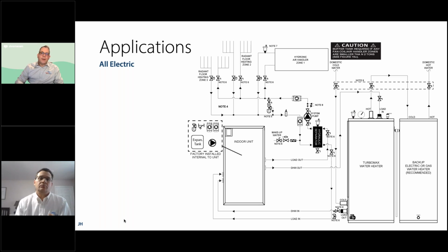So very simple piping. All of the hydronic components that are internal to the indoor module save a lot of time. And on any hydronic system, that's one of the biggest challenges. In this case, we've got to get over to that hydraulic separator, and from there, the piping is like any other system, really. And so we've saved quite a bit of labor in that case. This happens to be the all-electric version.